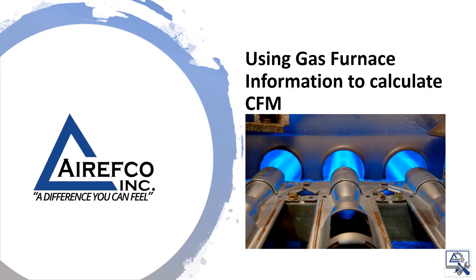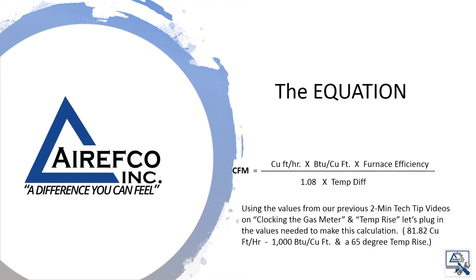In order to calculate CFM for a gas furnace we need some information to plug into the equation. The equation for CFM on a gas furnace is cubic feet per hour times BTUs per cubic foot times our furnace efficiency, divided by 1.08 times the temperature difference.